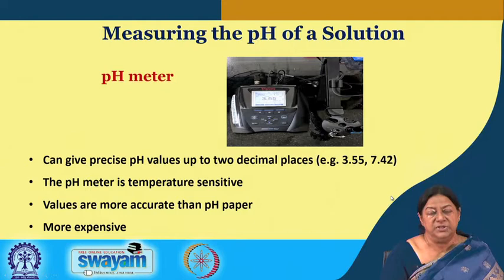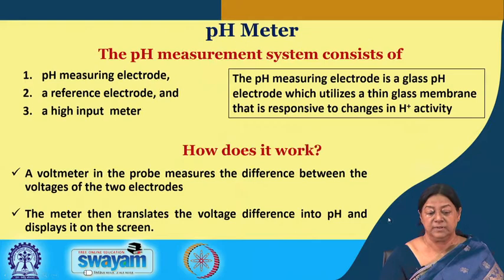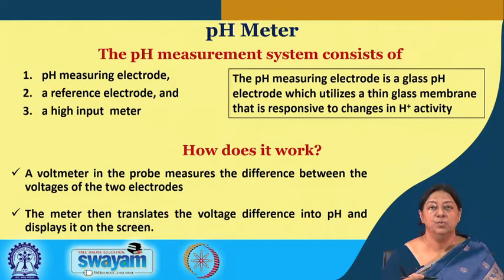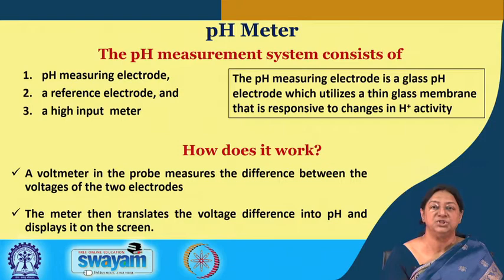We use a pH meter — its use will be demonstrated. It can give precise pH values to even 2 decimal places, which is sometimes required for biochemical reactions. The pH meter is temperature sensitive and gives values much more accurate than pH paper, though it is more expensive. The pH measurement system consists of a pH measuring electrode, a reference electrode, and an input meter. The glass pH electrode uses a thin glass membrane responsive to changes in hydrogen ion activity. A voltmeter in the probe measures the voltage difference between the two electrodes, and the meter translates this into a pH value displayed on screen.